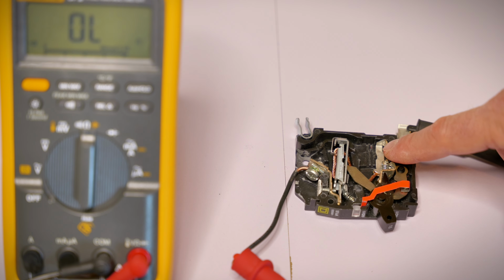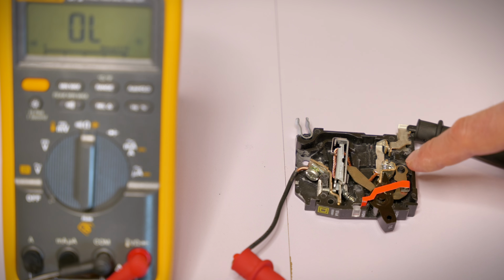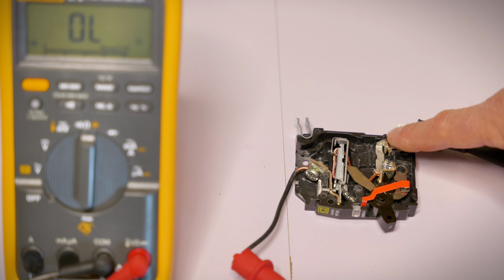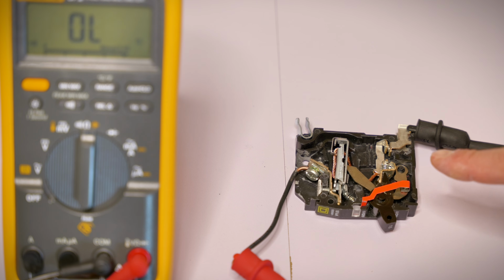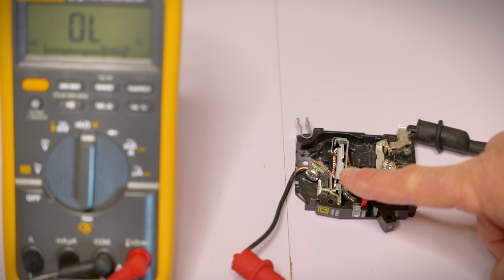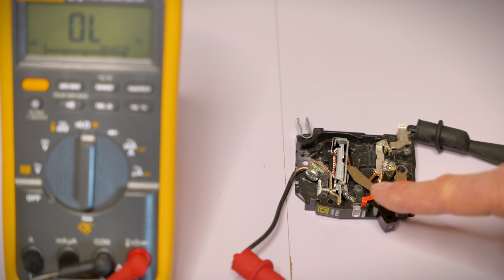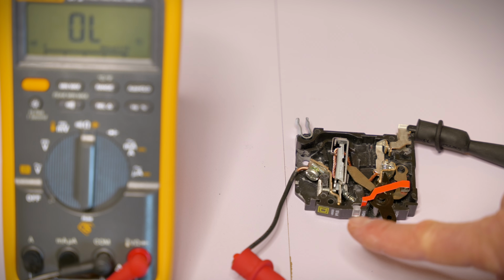The movement arm could be a little bent. It could have tripped and dislodged. There's a spring right there. Sometimes that spring can pop off. Anything could be preventing that contact from being made right there. If this is the case, then there's nothing really repairable, because to remove the cover, you really have to drill, so you're not going to be able to fix it. At that point, I would bring the old one with you to the store and replace that circuit breaker out.